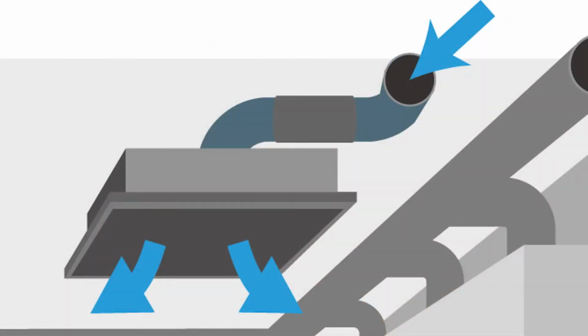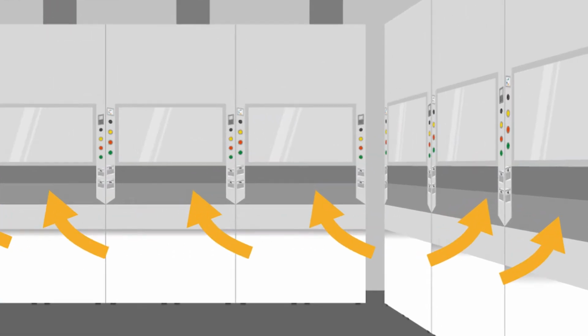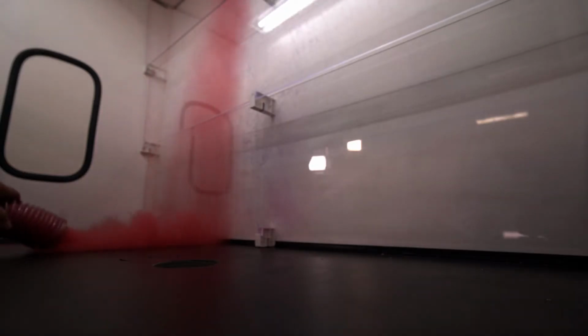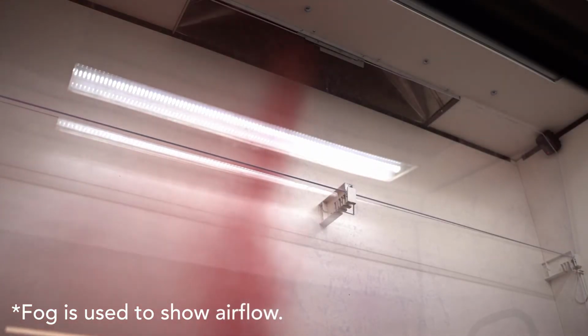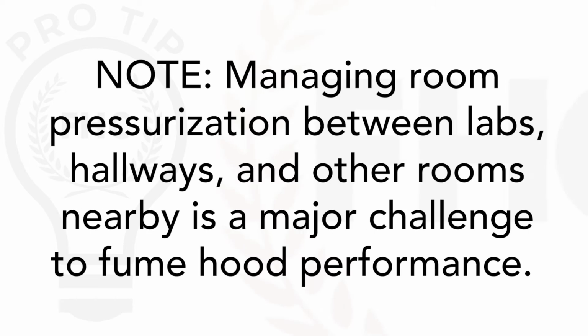Airflow is designed to flow from clean to dirty areas. The clean air from the corridor flows into the lab. The lab air flows into the hood through the sash opening, then into the plenum, then the ductwork to the exhaust fan where it's usually exhausted out of the building. Any imbalance can cause the direction of the flow to change. Managing the room pressurization is a real challenge to fume hood performance. Pressure changes can reverse flow, which can result in unsafe conditions in the lab. In a properly designed and balanced lab, the lab is under slight negative pressure compared to the hallway. If you crack the door, you usually can feel the air rushing in. The fume chamber has to be lower in pressure than the room to draw the air into the plenum.